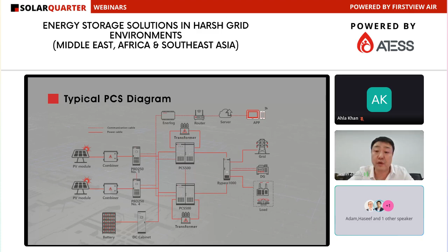For our AC side, we can see we have the grid, but as our topic today is about a very unstable, very bad grid, we can't count on the grid all the time. It doesn't matter - when we suddenly lose the grid, our battery is always online to supply the load while waiting for the grid to come back. If the battery is nearly finished but the grid is still out, we still have our diesel generator, or maybe a gas generator, some kind of generator connected to our system, or the PV power connected directly to our system, to continually supply our load while waiting for the grid to come back.